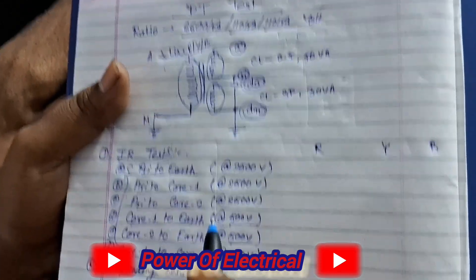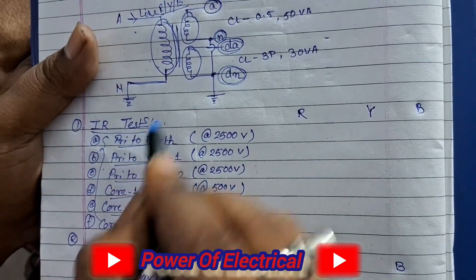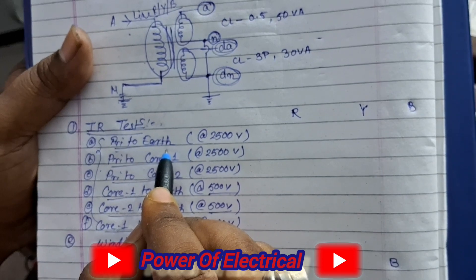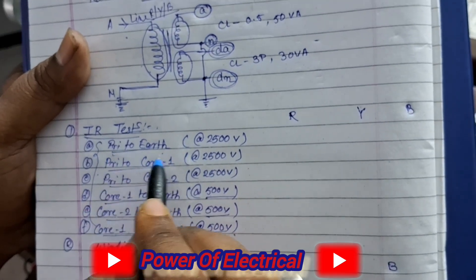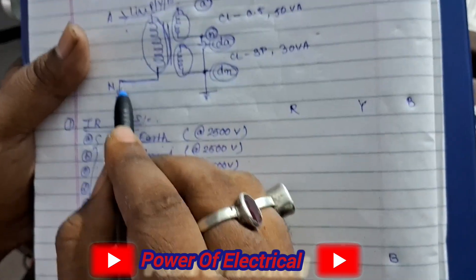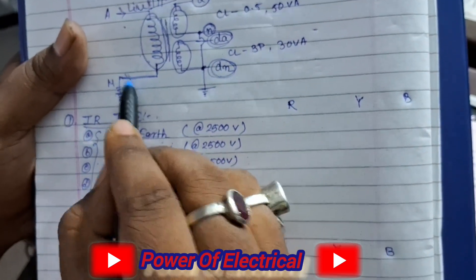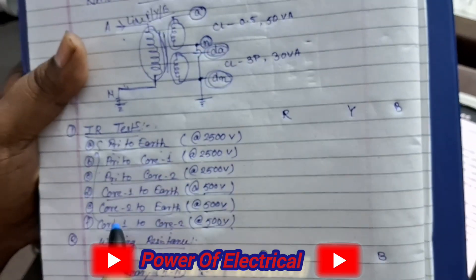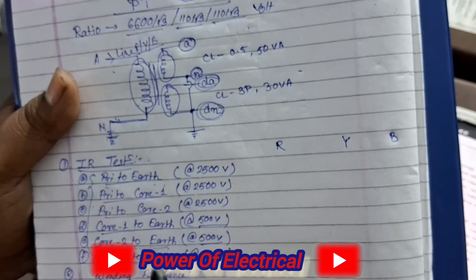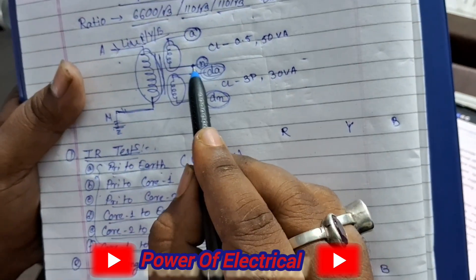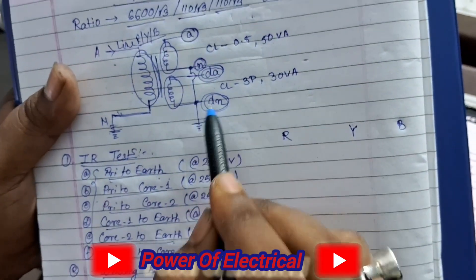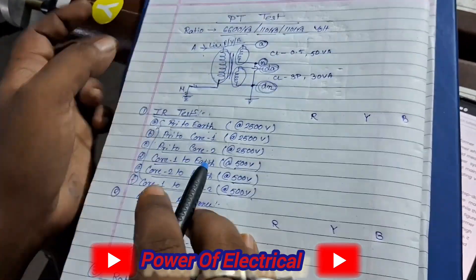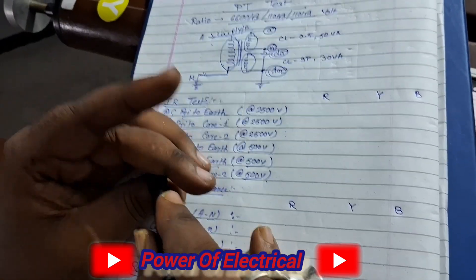For the IR testing, we need to remove the neutral link. When we perform the primary to earth megger test, we need to remove the neutral link. Similarly, when we do core one to earth and core two to earth megger tests, we need to remove the neutral link of small N and DN terminals. Now we are going to show practically how we do the test in the substation or power plant.